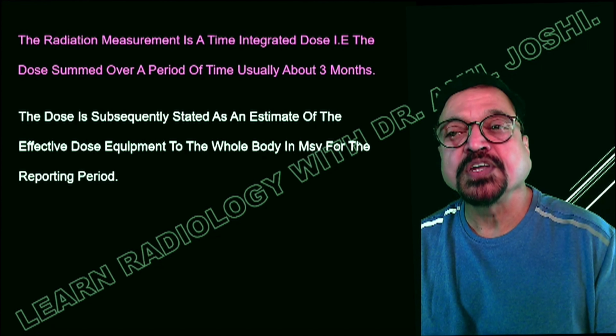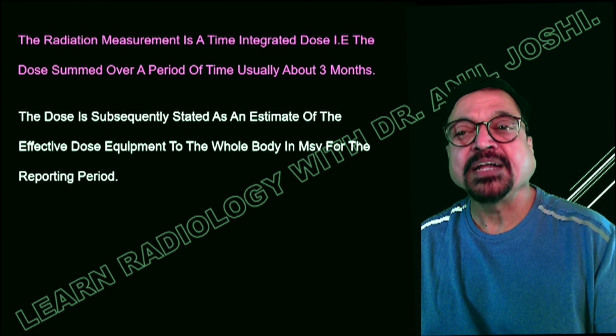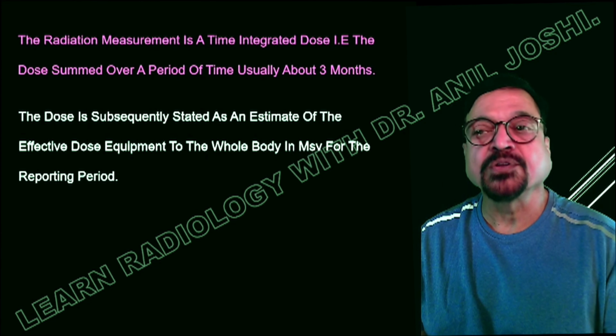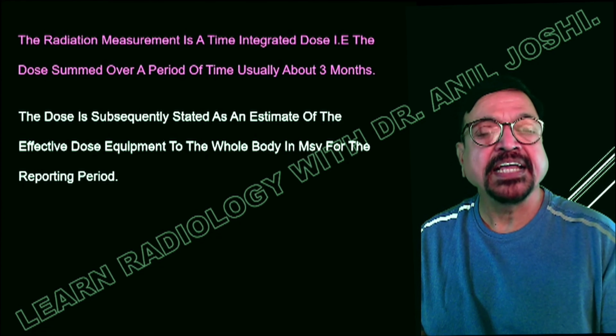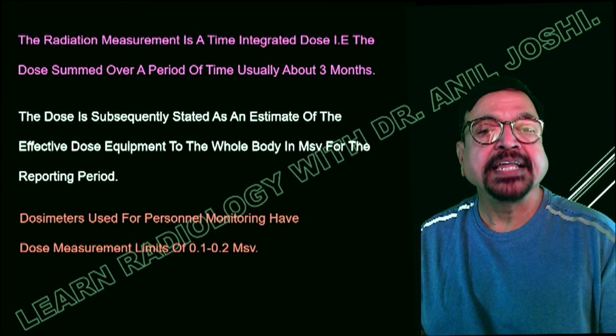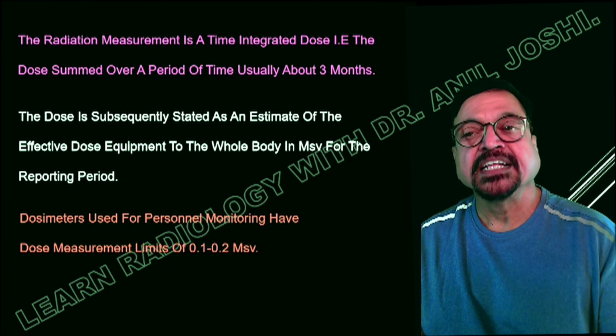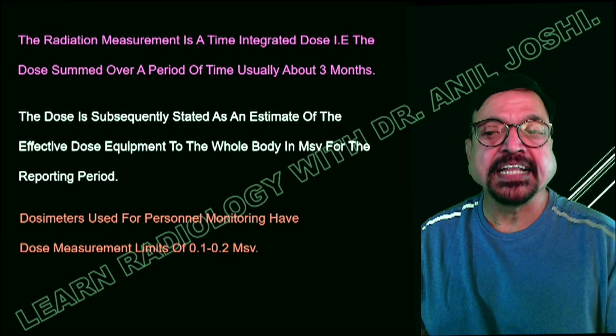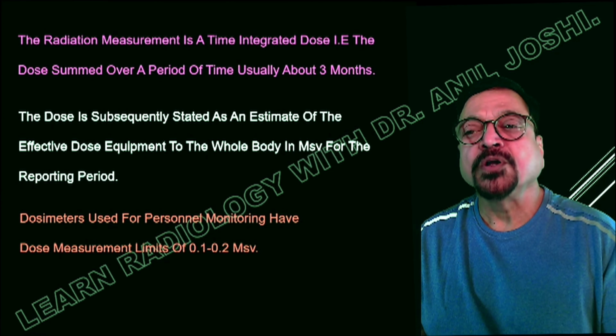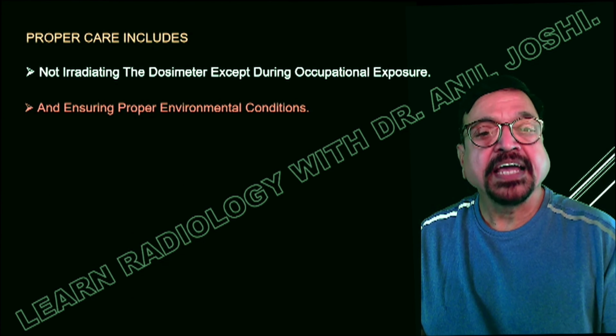The dose is subsequently stated as an estimate of the effective dose equivalent to the whole body in mSv for the reporting period, or for the period the person was exposed to radiation. The dosimeters used for this purpose are monitors, and their measuring limit is 0.1 to 0.2 mSv.